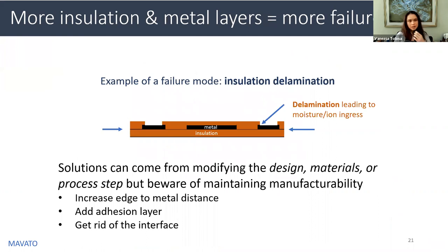That's because one well-known failure mode of polymer devices is delamination. You can get ion ingress from these salty, wet environments of the body, and when that happens, eventually your metal traces and electrodes will short and corrode, and you lose functionality of your device. I don't have time to go into this failure mode in detail, but it's an important note to make anytime you're talking about challenges in high channel count polymer-based microfabricated probes.